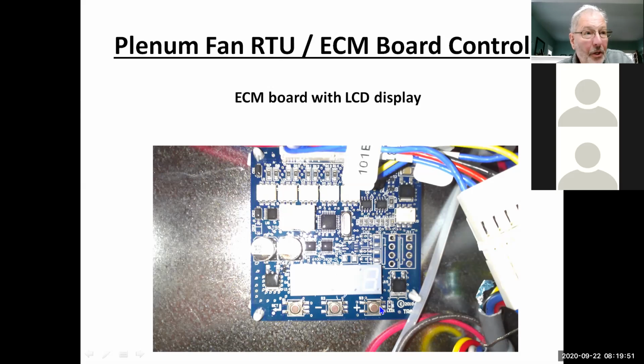And when you're done making your adjustment, you hold this button for 3 seconds again, and that remembers, or saves your change, and then the programming is done. So it's pretty simple to use. The display on here usually comes set at 5.0, which is 5 volts DC. And on our units, you can go anywhere from 5 volts to 7.5 volts, and the speed of this motor will change based on that.